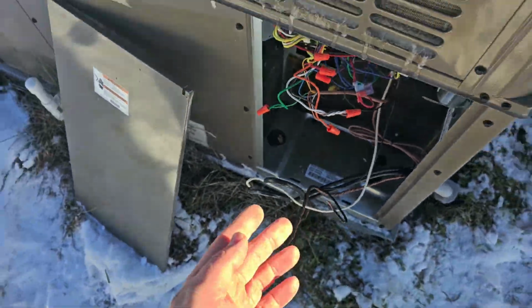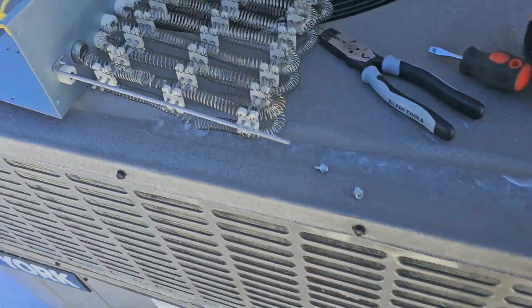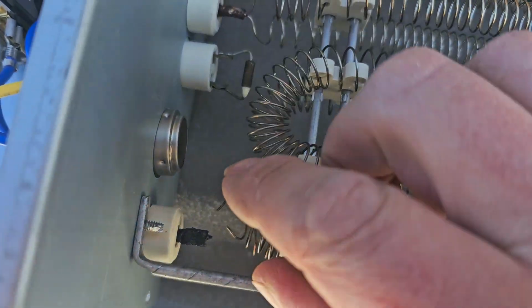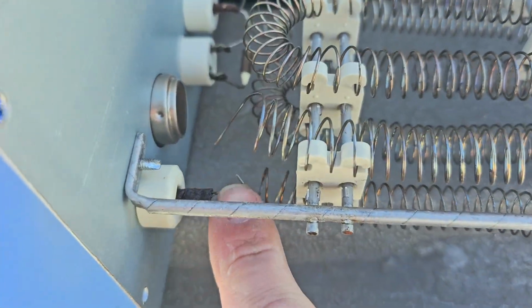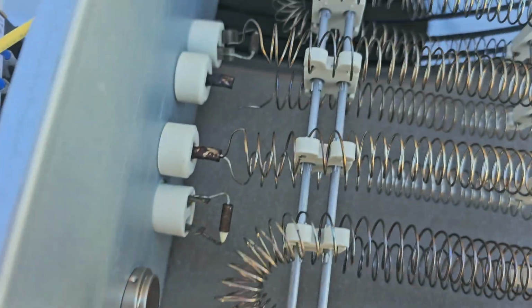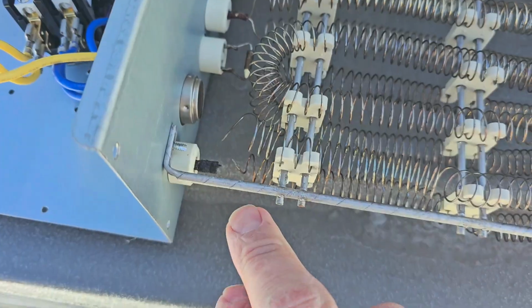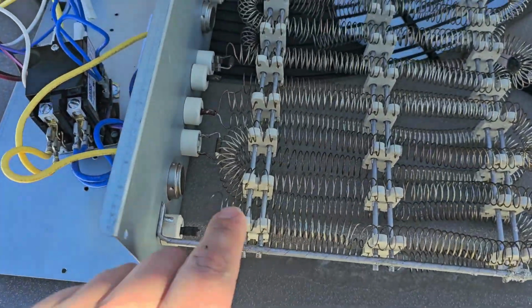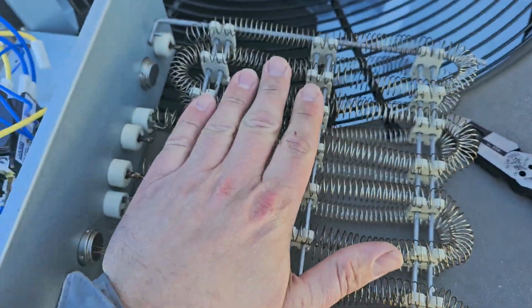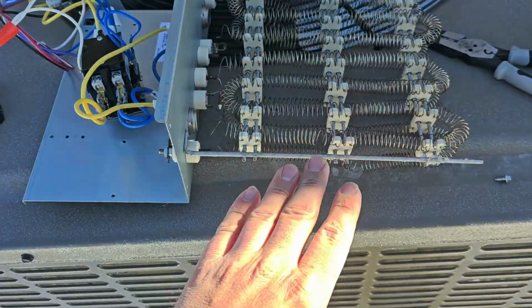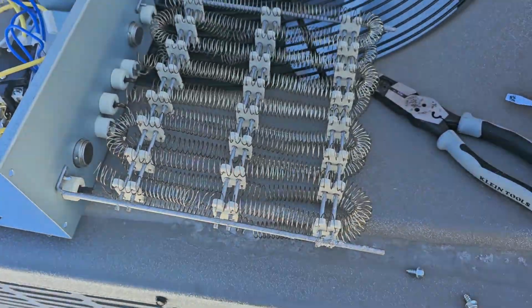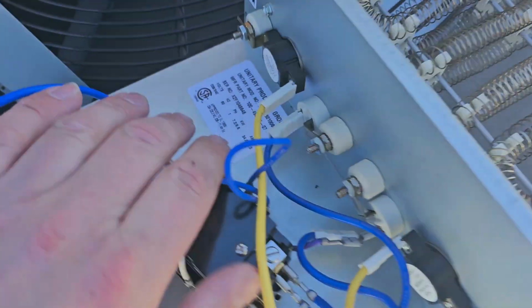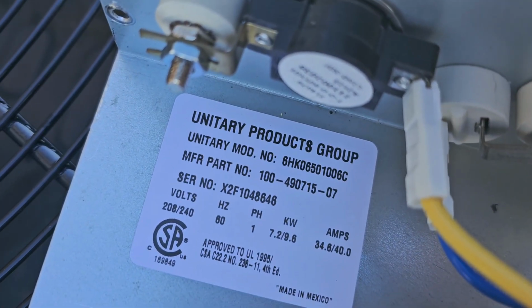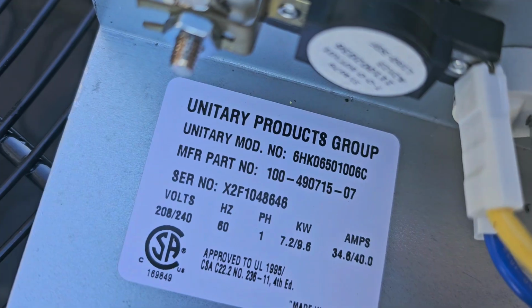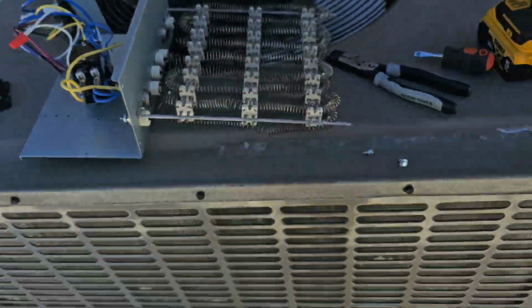I did verify that I had 240 volts going to the package heat pump and to the heater kit. And I don't run into this very often, but look at this. Wires are broken off. Look at that, wire broken off in the exact same spots. And that will cause the heater kit to not work, the heat strips to not glow because they're not getting power through them. So I need to get a new heater kit. What's the model number? 6HK0650106.